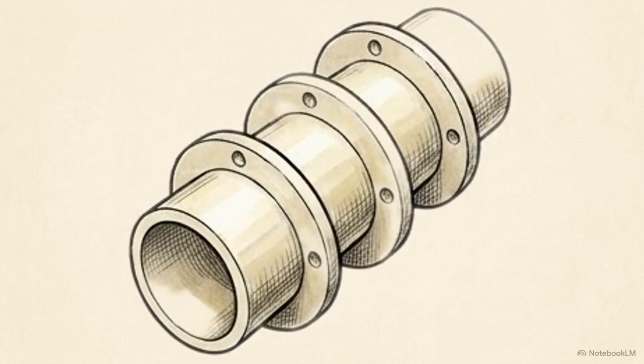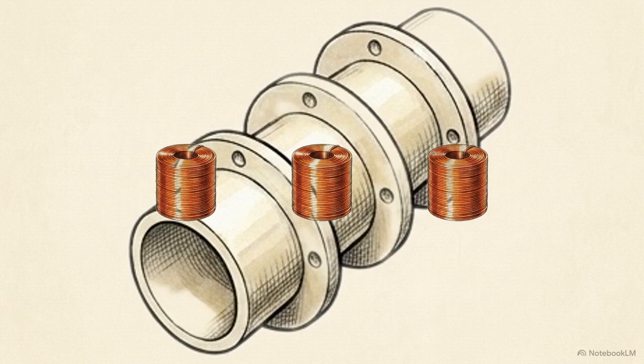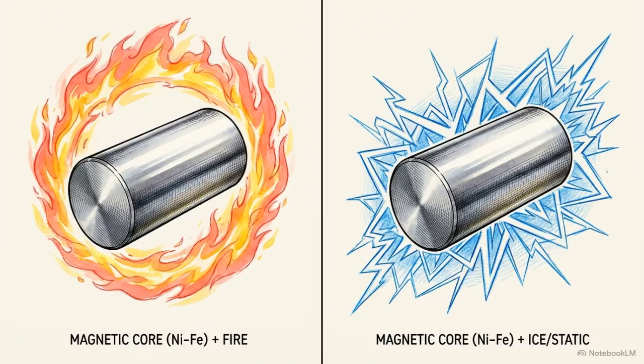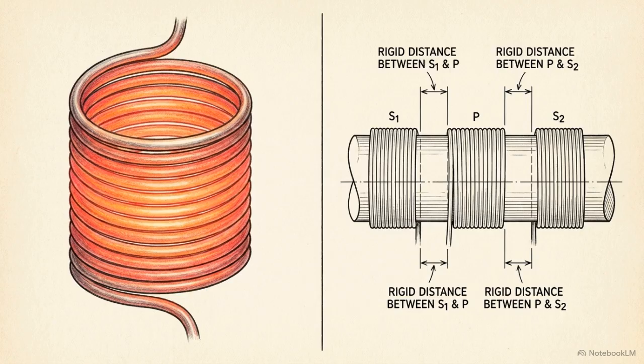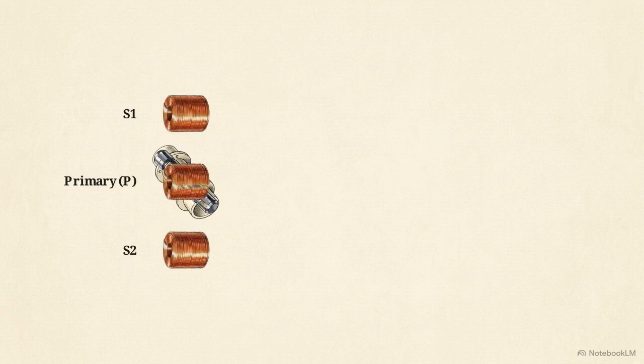This cross-sectional schematic reveals the LVDT's layout: 3 coils wrapped around a cylindrical former. The primary winding, labeled P, sits dead center. 2 secondary windings, S1 and S2, flank the primary, wired strictly in series opposition. A movable hydrogen-annealed nickel-iron core slides inside. Hydrogen annealing is a mandatory manufacturing step for this core. It eliminates harmonics and residual voltage, ensuring the transducer maintains a high signal-to-noise ratio. Unlike the RTD, which alters its own material structure, the LVDT relies on its physical geometry. The fixed layout dictates exactly how magnetic flux will behave when the core moves.